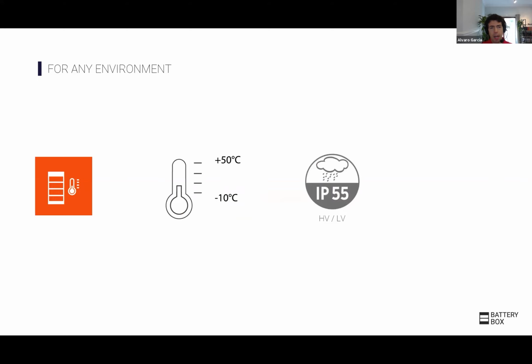The batteries can be installed outdoors, since they are IP55. However, take the IP level into consideration - they need to be somewhat covered from direct rain, direct sunlight, direct snow, etc. They can operate between -10 and 50 degrees. If the temperature is below -10, which I imagine some parts in Poland are right now, the system will not let you do the commissioning - it won't let you work until you're back within the temperature range.